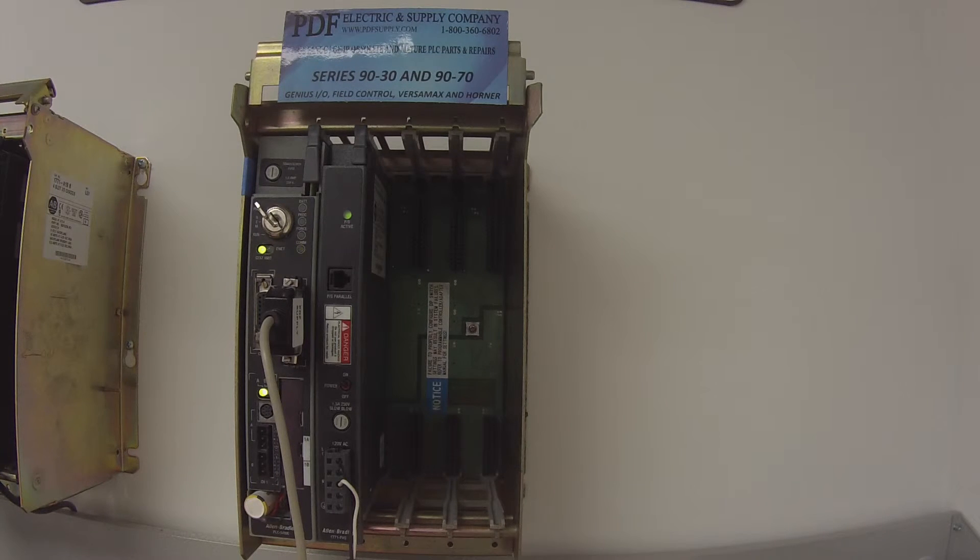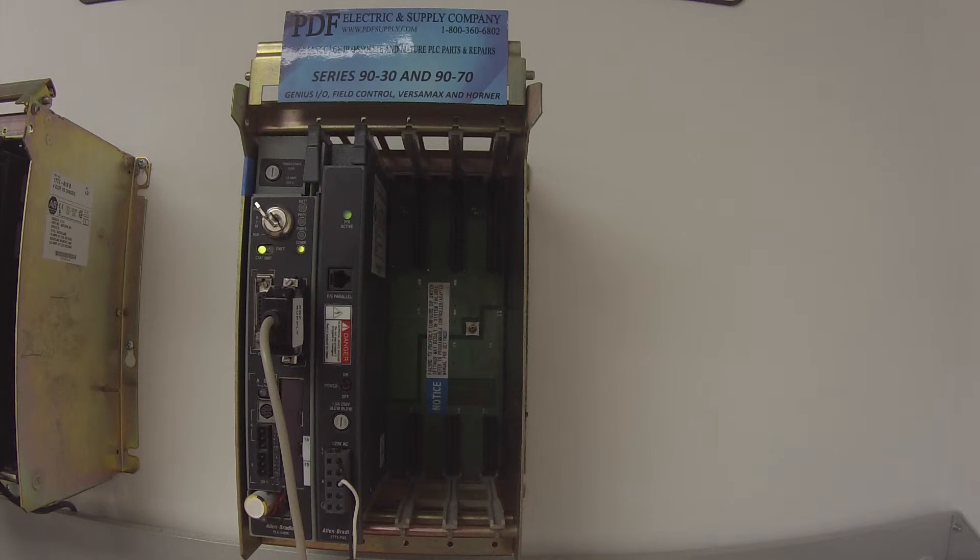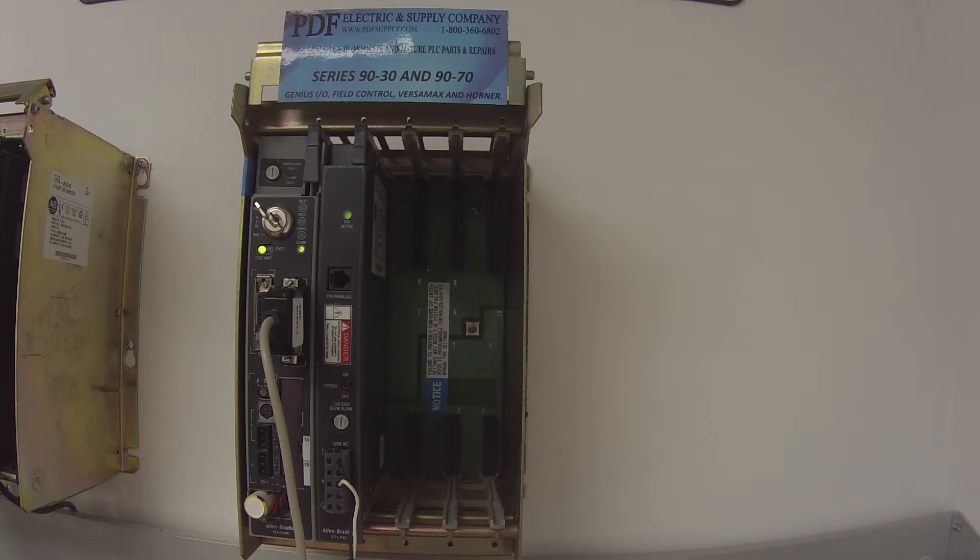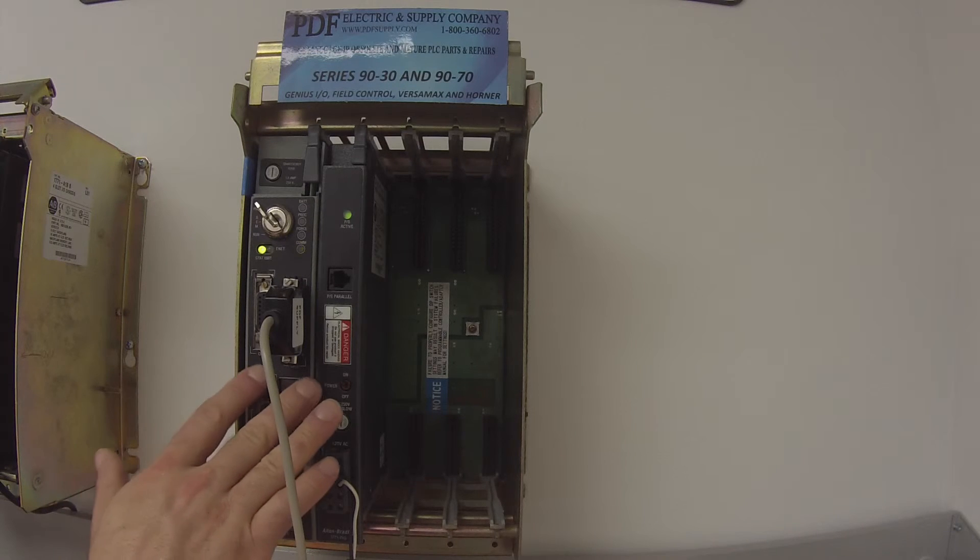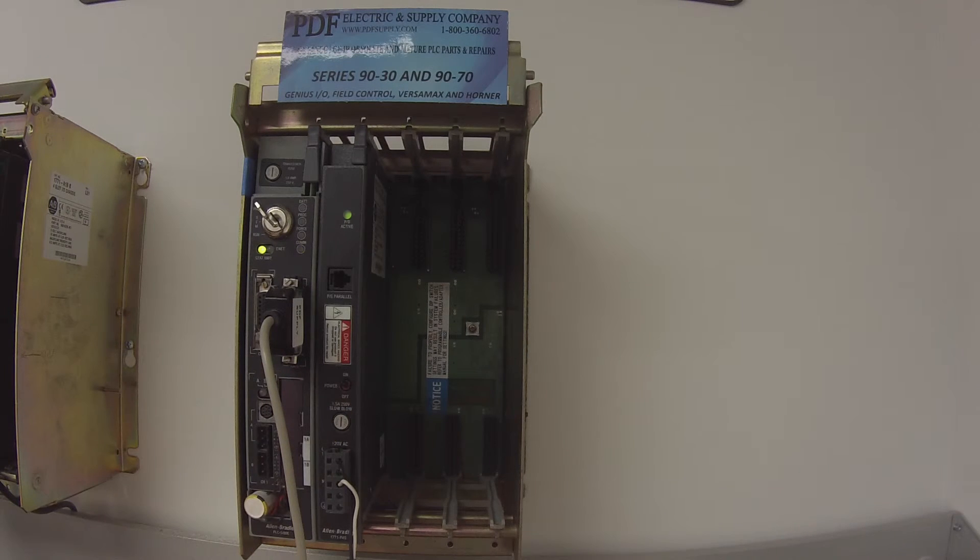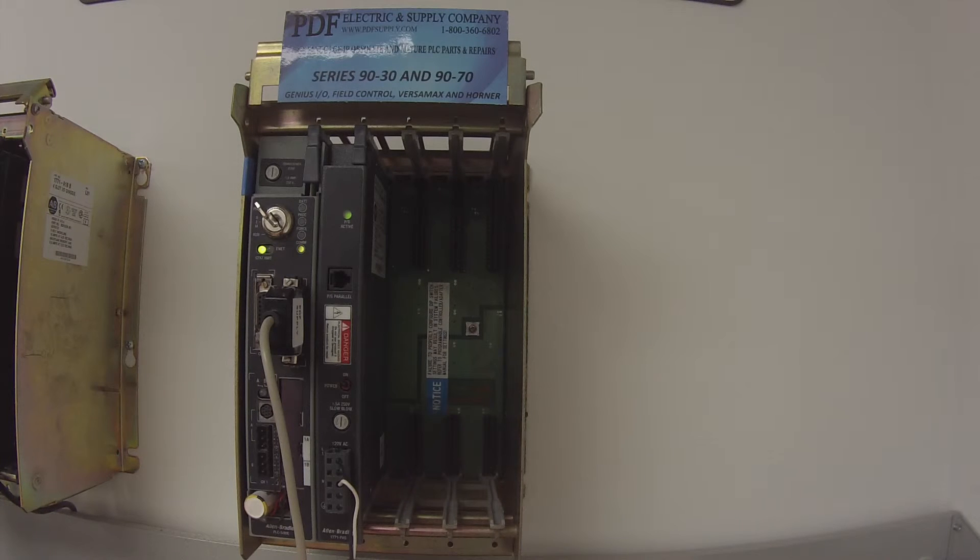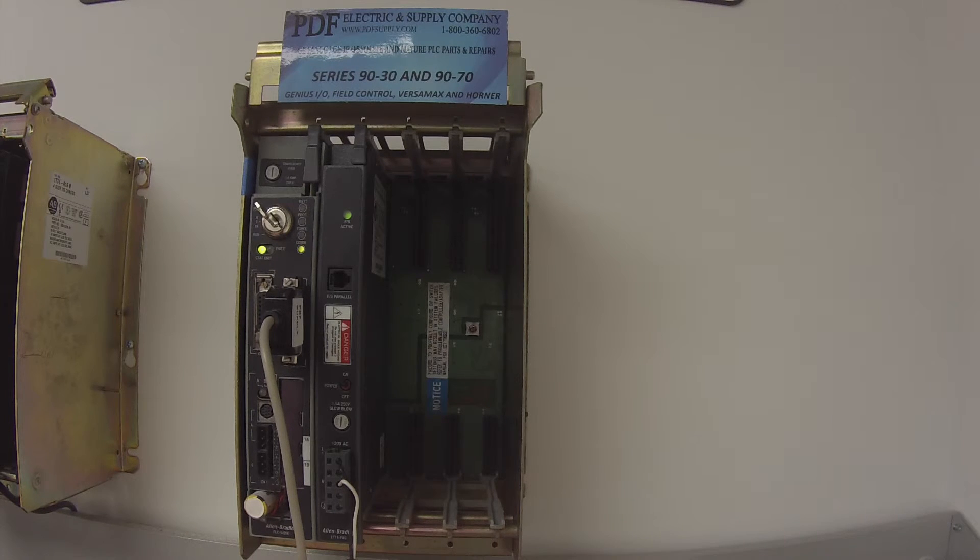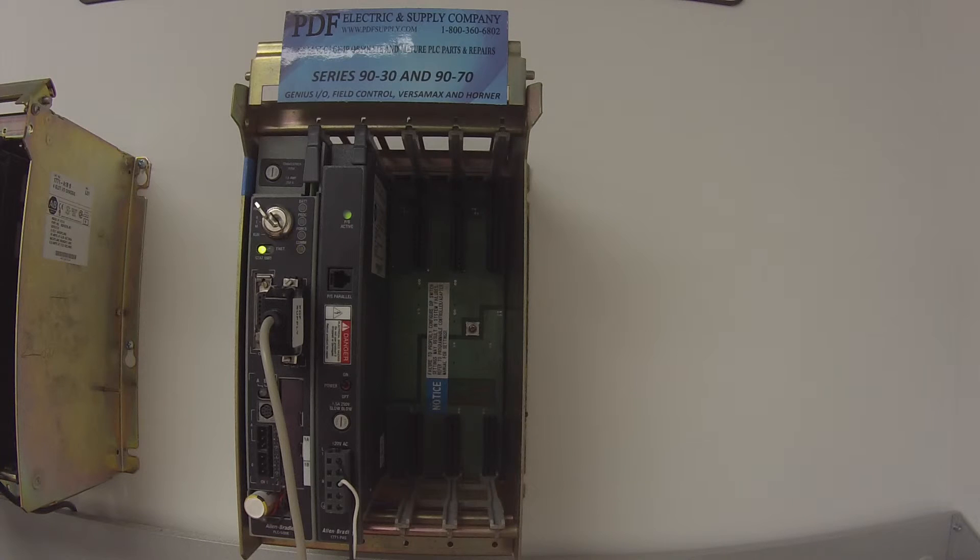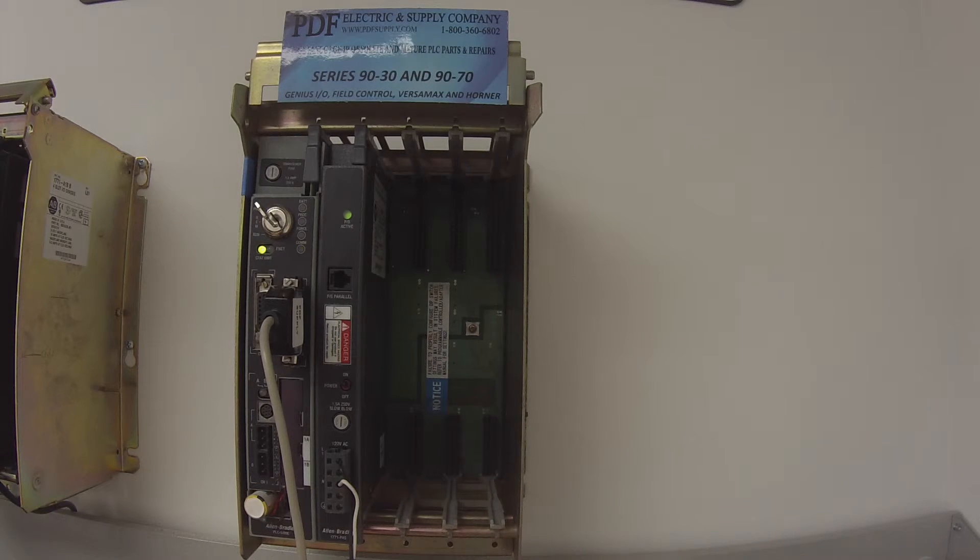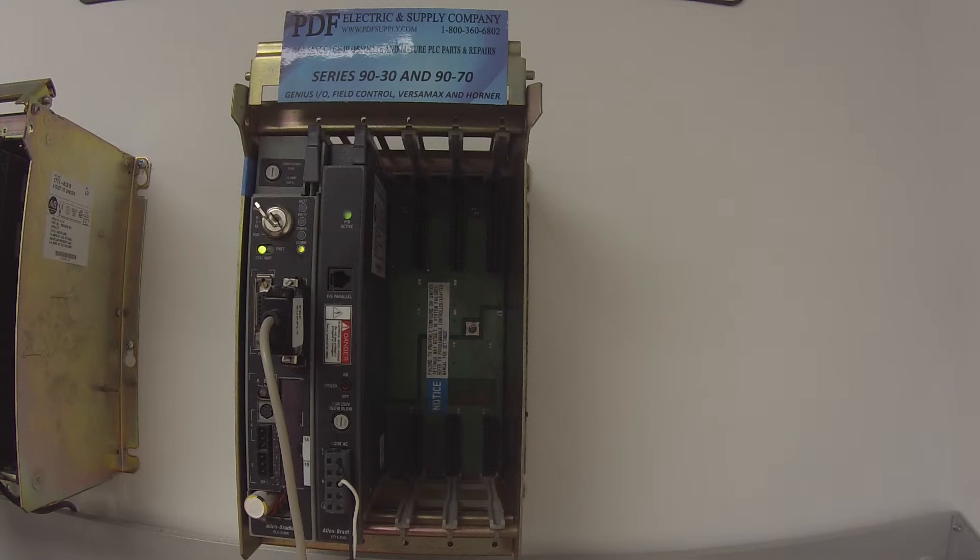And you'll also see a ladder with some green, pink, and blue squares revolving. And if it's revolving, it's telling you that this is all communicating and talking. If it stops and says that the processor's gone offline for some reason, that reason could be if you've changed your baud rate. You simply open your RSLinx Classic Lite and just hit auto-configure one more time and it'll get you back on track again.